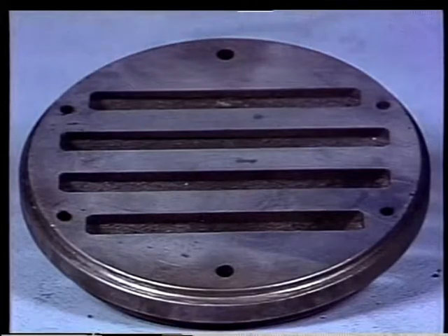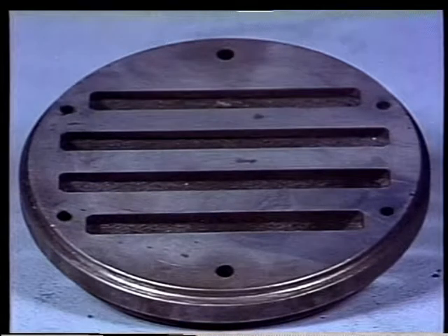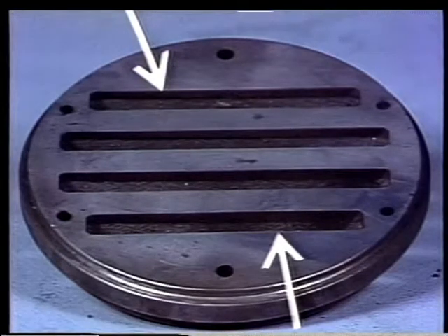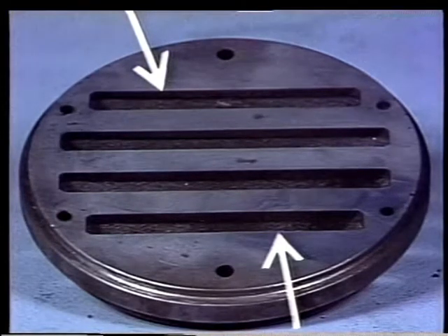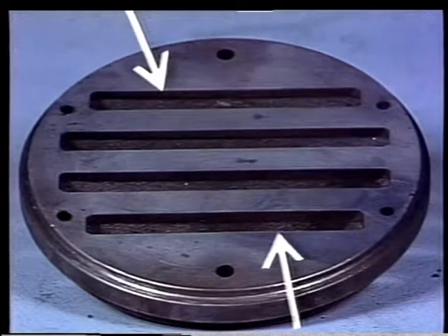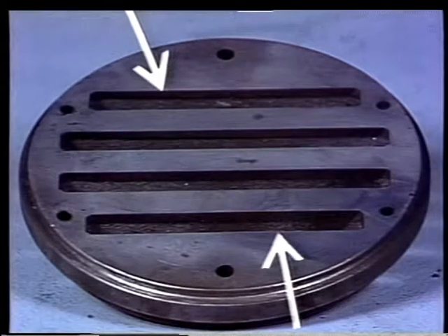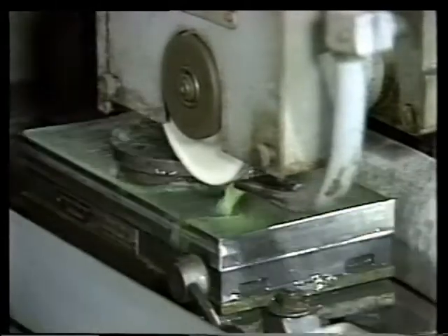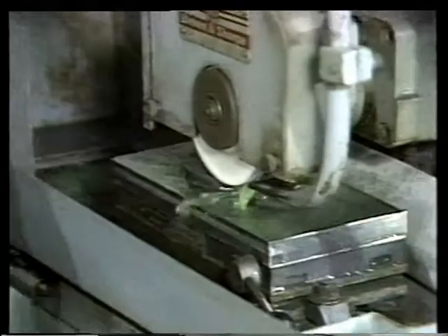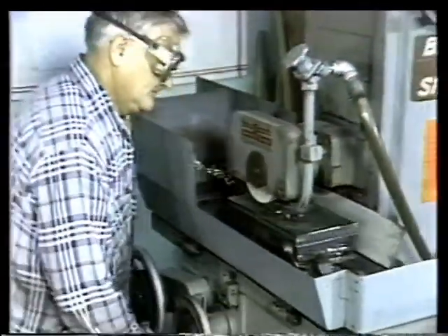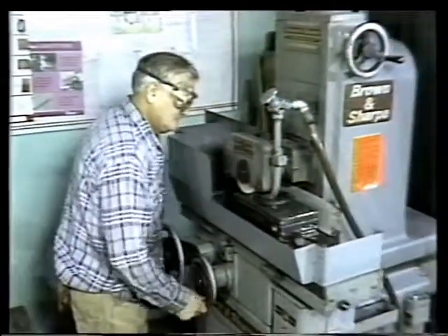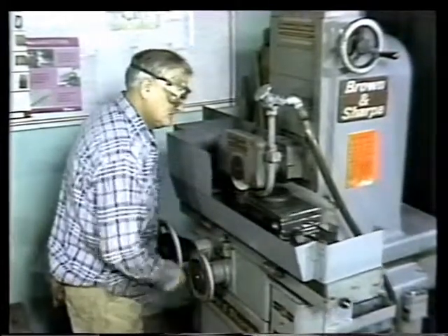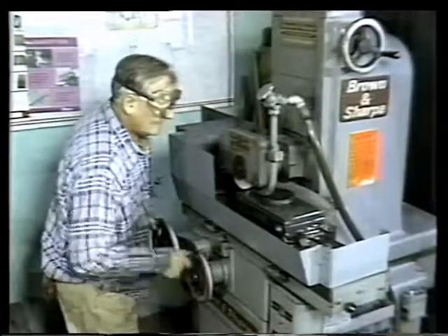After cleaning all the valve parts, inspect them carefully for any signs of wear, such as chips along the edge of the valve seat where the channel goes. If you find any wear along the seat, grind it to ensure a flat seating surface for the channels. Surface grinding is done on a grinding machine. It actually removes a fraction of the metal surface. And it tends to leave tiny scratches in the surface of the metal, which can interfere with the valve operation. So it's necessary to lap the surface to remove these scratches after the grinding is completed.